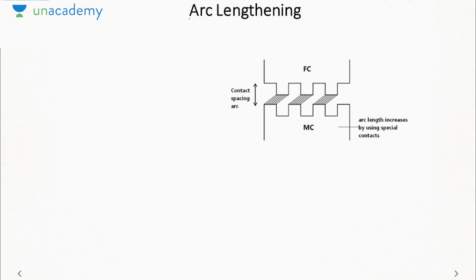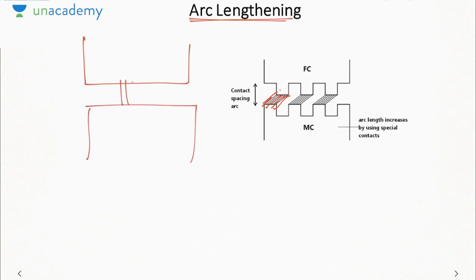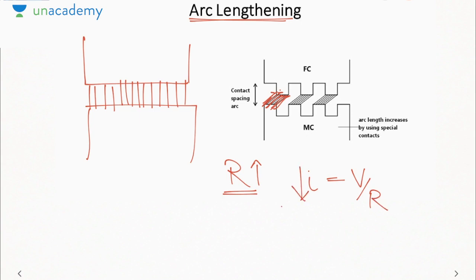Increasing the resistance involves increasing the length of the arc. How to do that? We form the circuit breaker plate something like a jigsaw puzzle, due to which the arc will have a higher length. Suppose the plates were initially like this, the arc will be like this. If the length of the arc is less, the resistance is less and arc current is high. But now the path taken by the arc has a higher length, so the arc resistance increases, due to which, since I equals V by R, arc current reduces.